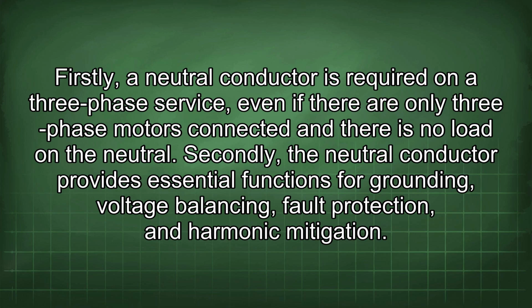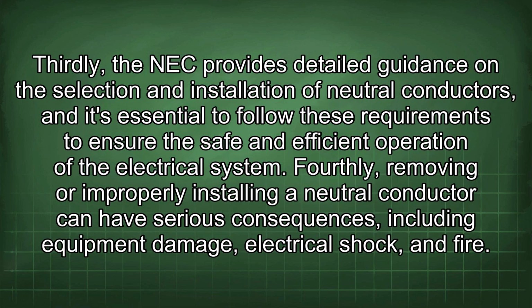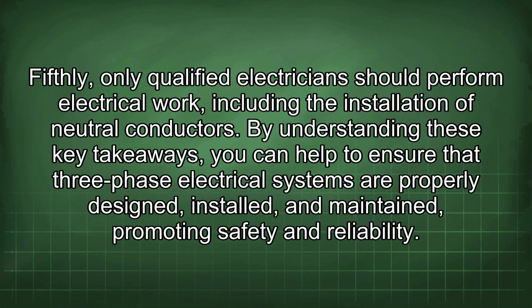Firstly, a neutral conductor is required on a three-phase service, even if there are only three-phase motors connected and there is no load in the neutral. Secondly, the neutral conductor provides essential functions for grounding, voltage balancing, fault protection, and harmonic mitigation. Thirdly, the NEC provides detailed guidance on the selection and installation of neutral conductors, and it's essential to follow these requirements to ensure the safe and efficient operation of the electrical system. Fourthly, removing or improperly installing a neutral conductor can have serious consequences, including equipment damage, electrical shock, and fire. Fifthly, only qualified electricians should perform electrical work, including the installation of neutral conductors. By understanding these key takeaways, you can help to ensure that three-phase electrical systems are properly designed, installed, and maintained, promoting safety and reliability.